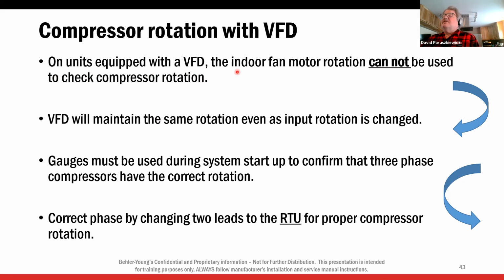All right. On units equipped with a VFD, the indoor fan motor rotation cannot be used to check compressor rotation. Again, the blower is running the correct direction no matter what. So if the blower is running the right direction, don't assume the compressors are.